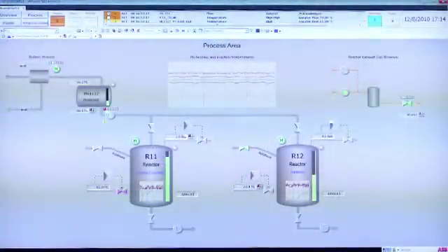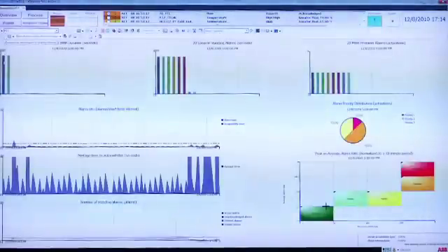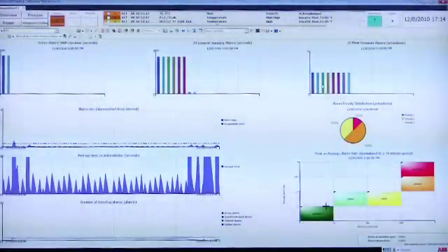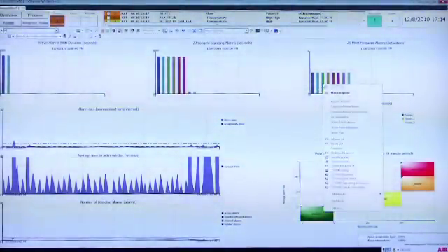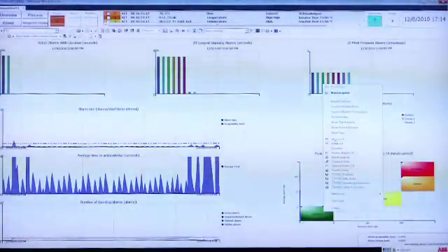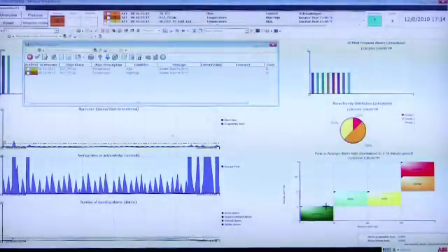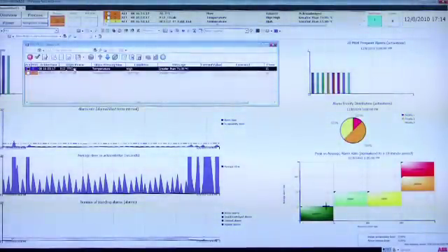And since these alarm displays are all graphic elements, they can be combined into one alarm performance indicator graphic. The alarm statistic graphic displays also allow you to navigate to the tags for further investigation and action. For example, by right-clicking in the 20 most frequent alarms display, you can navigate to the tags aspect menu and call up the tag alarm list.